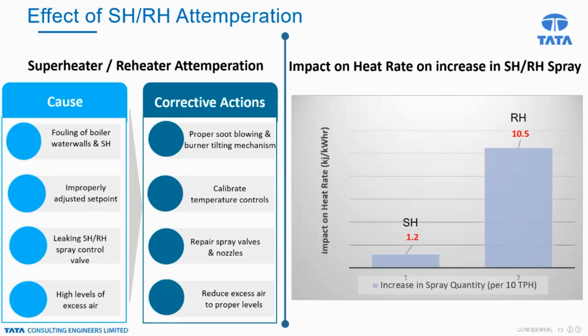Obviously, there are corrective measures that should be taken during operation: proper soot blowing and the burner tilting mechanism. If we have a tangential firing system, the burners would have a tilting mechanism, and proper burner tilting will give less spray water in both the superheater circuit and the reheater circuit. Calibrate the temperature control, repair the spray water valve so that we can avoid passing of the spray control valve, and reduce the excess air to the proper level. We should always operate the boiler as close to the specified excess air as possible, because any additional excess air will increase the flue gas quantity, which in turn increases the dry flue gas loss, and the boiler efficiency will drop.